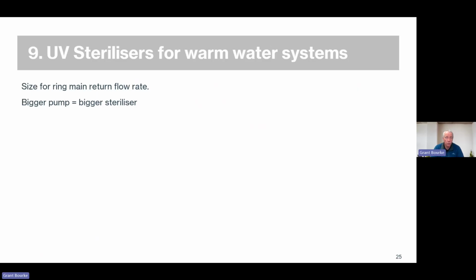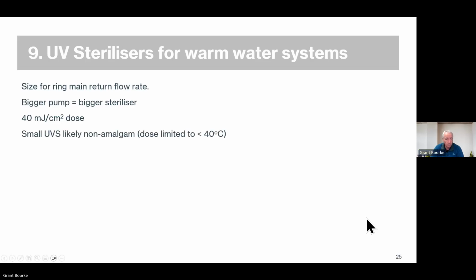The quicker the water is going through the UV sterilizer, the less it gets bombarded with UV and killing the bugs. If you put the water through it faster, the water is not next to the UV for as long a time and it doesn't sterilize as well. So we don't want to go silly on the pump size, because then our UV sterilizer will also get really big. So we're looking for about a 40 millijoule per centimetre squared dose. That doesn't mean anything other than that's the column you want to look up in your UV supplier's catalogue.